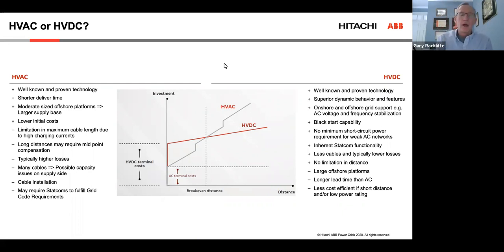longer cables. There is an advantage with HVDC where you can control the power flow. It can perform the functions of a STATCOM, so you can control the angle and power factor. You can inject reactive power if need be, and it also supports black start. But we see the deployment of both high voltage AC and high voltage DC. And here we show both the benefits for each, as well as some of the challenges that each technology represents.